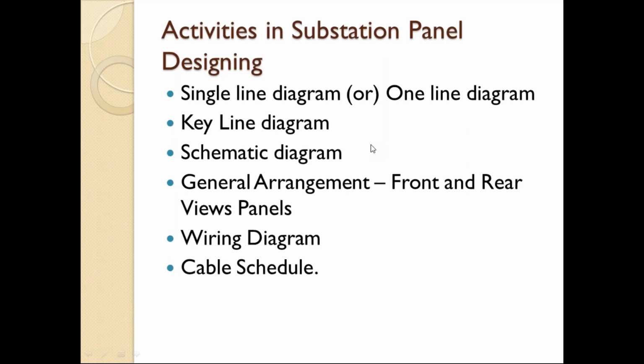We are doing transformer replacement jobs for several projects. In these up to 400 kV substations, there are only the transformers. So if the transformer is removed and a new transformer with some 240 MVA is put in, we need to identify what changes and modifications are needed to the existing drawings, and produce them.